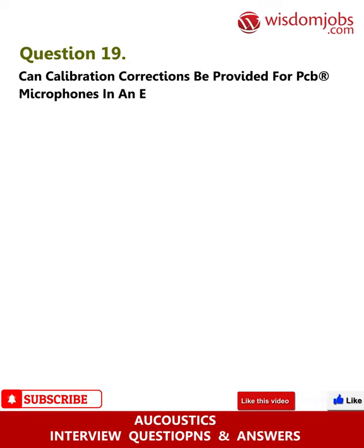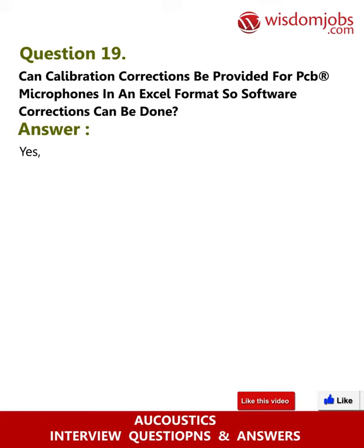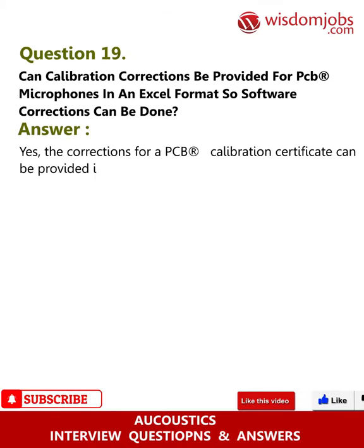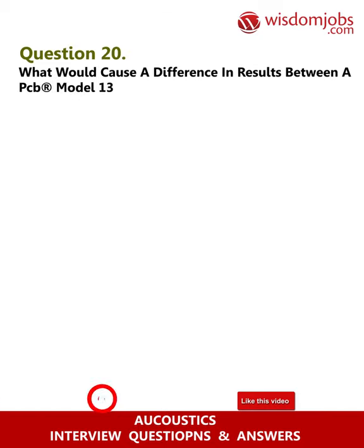Question 19: Can calibration corrections be provided for PCB microphones in an Excel format so software corrections can be done? Answer: Yes, the corrections for a PCB calibration certificate can be provided in Excel format.